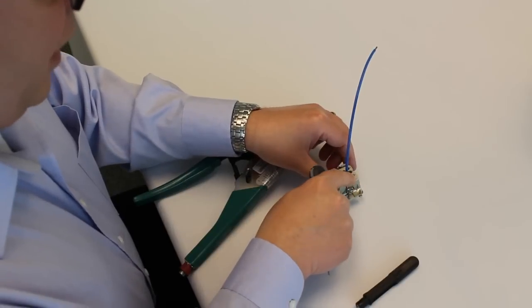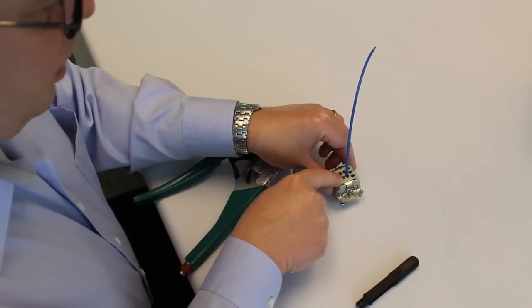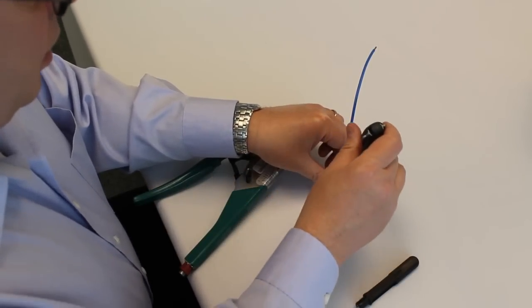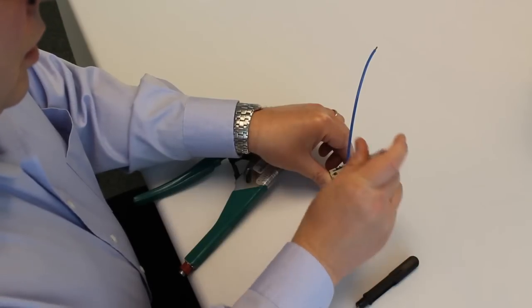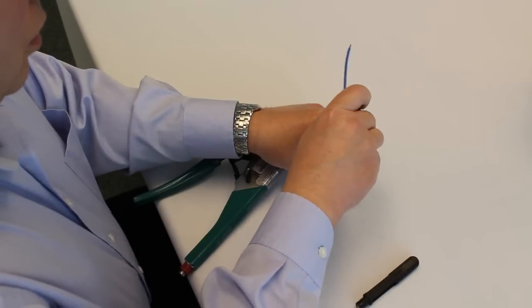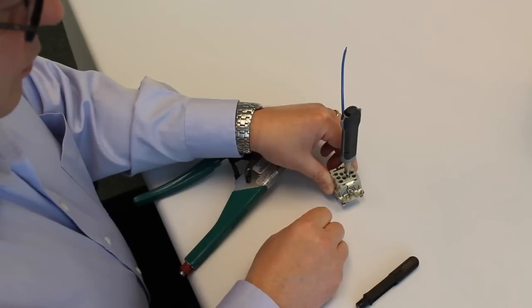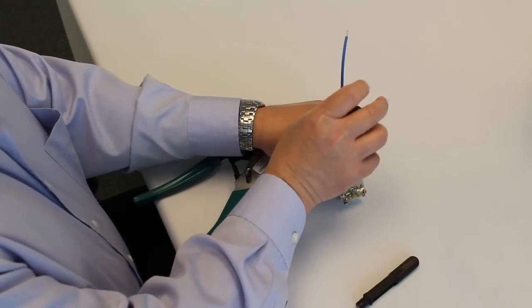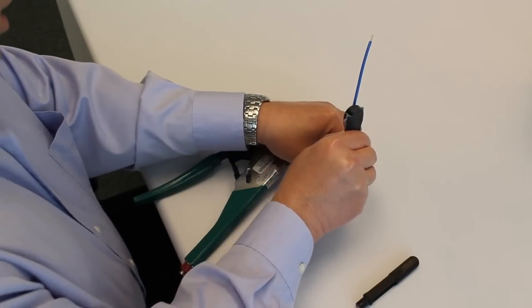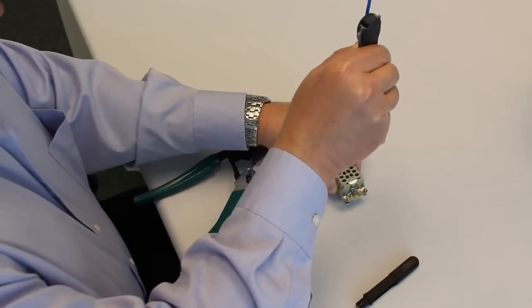You'll notice by every contact cavity, there's a slot at the side. You insert the removal tool until it comes to a stop. You clamp the wire against the side of the tool, and remove it to the rear.